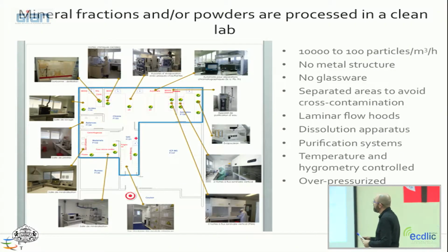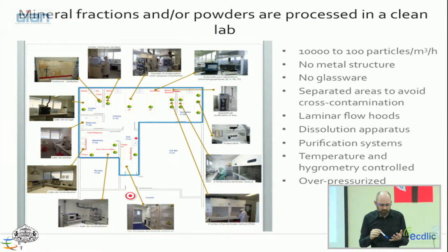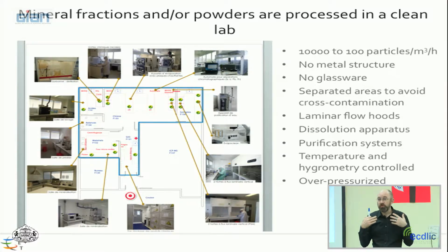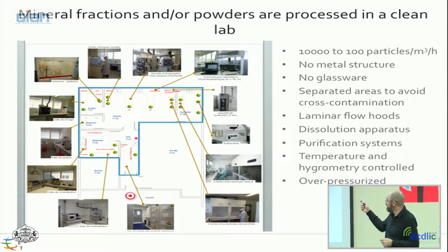So typically, this is the lab the way it was designed in Toulouse. We are going to extend it, I mean, double it, but the philosophy of a clean lab is basically overpressure. Totally the opposite to, for example, a biological clean lab. In a biological clean lab, you don't want the germs to escape your lab. In geology, you don't want the germs to enter the lab. Yes, and so it's overpressure. It means that you don't want dust to enter, and nothing from the outside should enter into the lab.